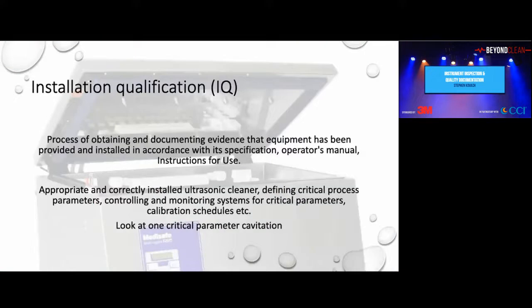This is the process of obtaining and documenting evidence that equipment has been provided and installed in accordance with its specifications and instructions for use - appropriately and correctly installed ultrasonic cleaner, defining the critical process parameters, controlling and monitoring systems for critical parameters, calibration schedules, etc. We're only going to look at cavitation.